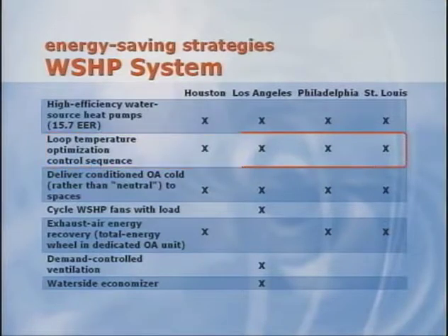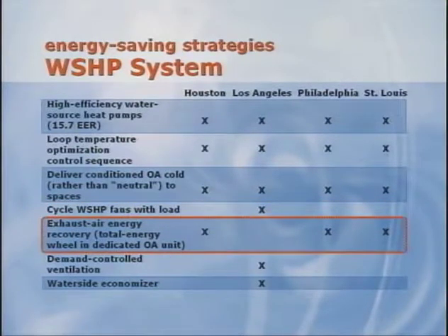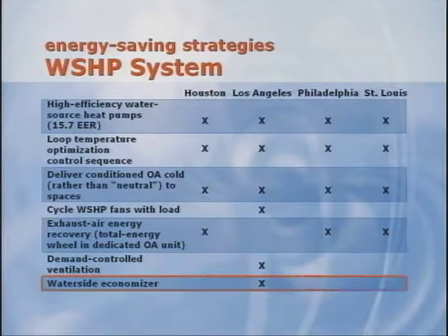Similar to the fan coil system, the conditioned outdoor air is delivered cold rather than neutral directly to the space. As John mentioned, this can allow the heat pumps to be downsized and save energy. And if the outdoor air is delivered directly to each space, the fan inside the heat pump does not need to operate in order to ventilate the space. This affords the opportunity to cycle that local fan on and off along with the compressor, saving fan energy at part load conditions. This strategy was used for the proposed building in Los Angeles. Next, for 3 of the locations, a total energy wheel was used to precondition the entering outdoor air. And finally, for LA, a waterside economizer was used on the heat pumps.